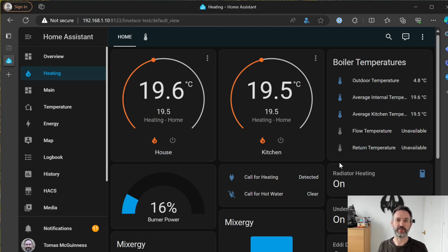The first consideration is how much power the boiler is going to put in, or how much heat we're going to put into the house. Now, I run my boiler at a flow temperature of 40, so that keeps the boiler's output basically at its minimum almost all of the time. It's a 35 kilowatt boiler, so it's massively oversized. So it can go down to about 5,800 watts at its absolute minimum.